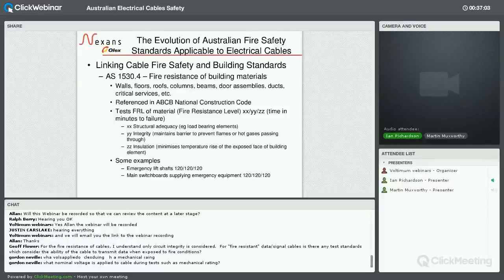Okay, there's another question there, Martin, from Gordon. What nominal voltage is applied to cable during tests such as mechanical rating? That's a good question. Because you're not going to apply 240 volts during the mechanical rating, because there'd be some safety issues concerned with that. So normally the mechanical rating is done at a lower voltage. The impact test is done at voltages between 18 and 30. And similarly for the cut test. When I was researching this, I was asking myself the same question, and it's quite interesting. They're done at much lower voltages for safety reasons, because there's a potential that the apparatus for testing the cable may become live.